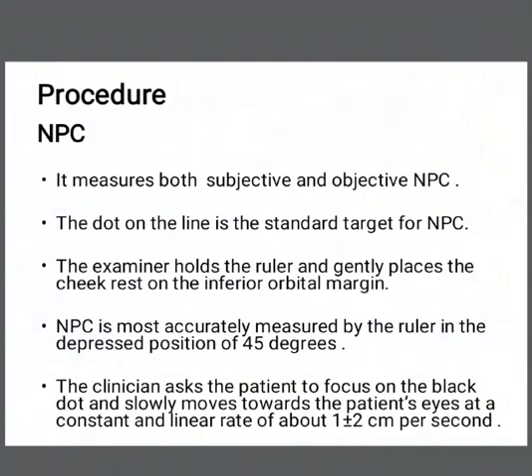Procedure — Near Point of Convergence: The RAF Ruler measures both subjective and objective near point of convergence. The dot on the line is the standard target for measuring near point of convergence. The examiner holds the ruler and gently places the cheek rest on the inferior orbital margin of the patient. Near point of convergence is accurately measured by the ruler in the depressed position of 45 degrees. The examiner then asks the patient to focus on the black dot and slowly moves it towards the patient's eye at the rate of 1 to 2 centimeters per second.